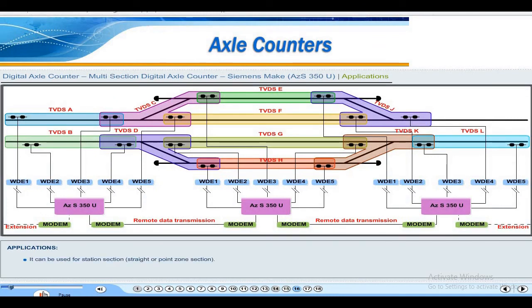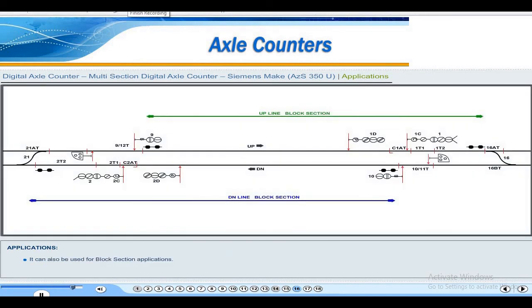Applications. It can be used for station section, that is straight or point zone section. Its evaluator can detect a maximum of 5 counting heads, that is EZP43 connected directly, or else a maximum of 6 EZP43 connected remotely. It can detect a maximum of 4 track vacancy detection sections, that is TVDS. It can also be used for block section applications. Limitations. For smaller applications, that is 3 or 4 detection points, it becomes costly. A longer length of communication cable is required for connection of outdoor equipments with the central evaluator.